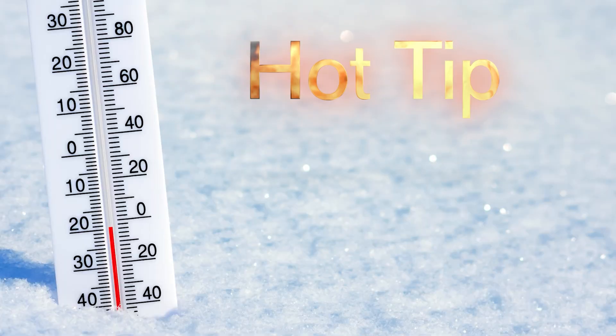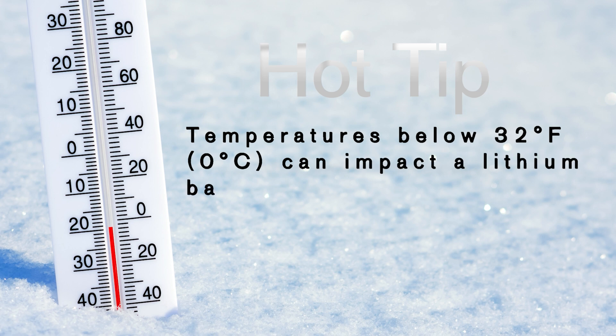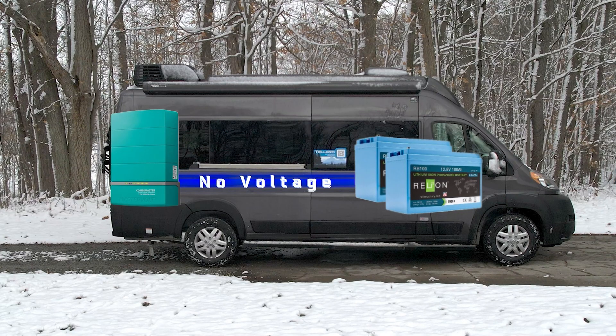Here are a few tips for using the RELiON batteries in cold weather. Outdoor temperatures below 32 degrees Fahrenheit can impact a lithium battery's ability to take a charge. The RB100LT battery must disable the discharge circuit when the heating element inside the battery is active. During this time, the inverter charger is not going to sense the battery voltage — it's only going to see the load of the heating element, not allowing the charger to reach the correct charge voltage.